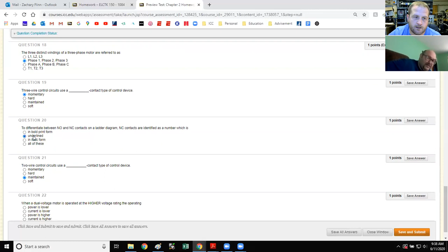To differentiate between normally open and normally closed contacts on a ladder diagram, normally closed contacts are identified as a number which is underlined. I don't know, you're alone on this one. I'll show you on a ladder diagram here in a minute. It's never been the issue. They've all been NC and NO, or the picture will actually show them normally open or normally closed. I've never seen them underlined. I'll find an example.